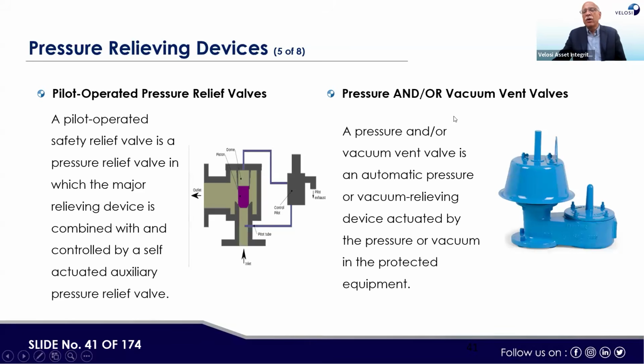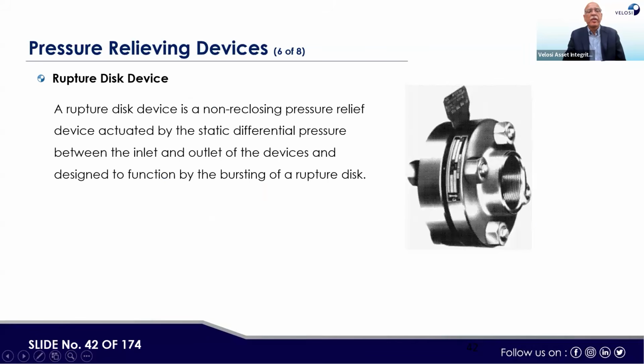Similarly, these are the vacuum or the pressure vent valves, where it works two-way. At high pressure, it goes up, and at low pressure, the air or the gas can come inside also. Then a rupture disc, it is just like a plate, and if pressure goes more than a certain limit, it bursts. So this cannot reset. So in case of the rupture disc, we have to replace it once it is ruptured.